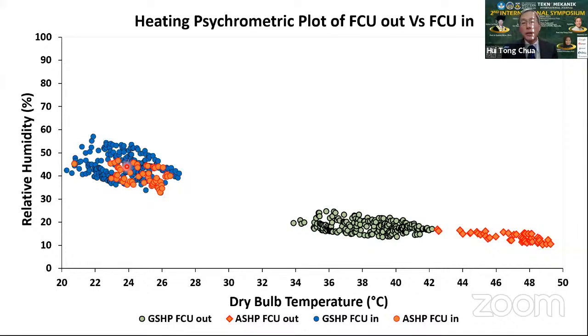But interestingly, in order to sustain heating for the air source heat pump unit, the fan coil unit outlet temperature is significantly higher than that of the ground source heat pump. This signifies that the ground source heat pump delivers a higher airflow rate for the same kind of enthalpy difference, which also points to the likelihood that the heat transfer coefficient between the ground source heat pump and the fan coil is higher than that of the air source heat pump.